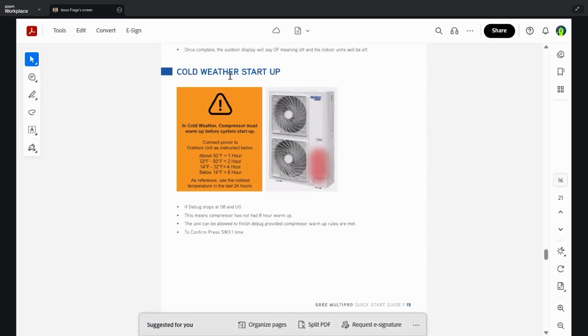One of the other things that we like to mention is the cold weather startup, especially now that we're in October. This is very crucial for compressor and compressor life. In cold weather, the compressor must warm up before system startup. Connect power to the outdoor unit and follow the chart below. So before, we recommended an 8-hour warm-up period, but that's no longer necessary. We have actually, along with the factory, come up with the actual values and actual duration of the compressor warm-up, depending on the temperature in the area or the outside environment.